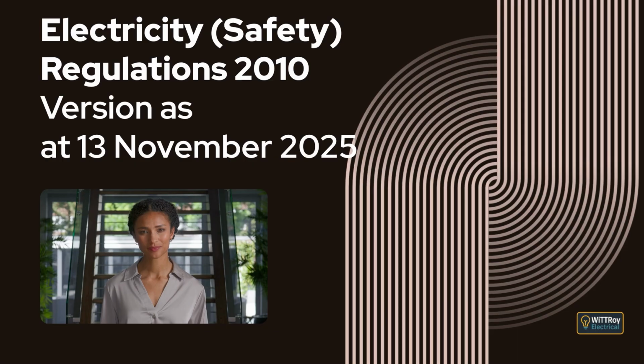This regulation explains what information must be included on a certificate of compliance. It explains that the certificate must confirm that the prescribed electrical work has been done lawfully and safely, that the information on the certificate is correct, and that the required regulatory information is provided and properly authenticated. It also explains that the certificate must include information confirming the work was done lawfully and safely, that testing has been satisfactorily completed, that the installation or part installation is electrically safe, and that the work has not adversely affected the safety of the installation or any fittings involved.